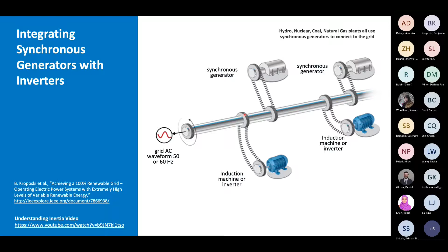When we connect other types of devices, like induction machines or inverter-based technologies, they don't have the same makeup as a synchronous generator, so they have a different physical coupling to the large power grid. We want to design inverters for PV systems, wind plants, and battery plants so they mimic some operational controls of synchronous generators, responding quickly to events and replicating those inertial characteristics. We really need to unify the operation between synchronous generators and inverter-based resources at any scale.